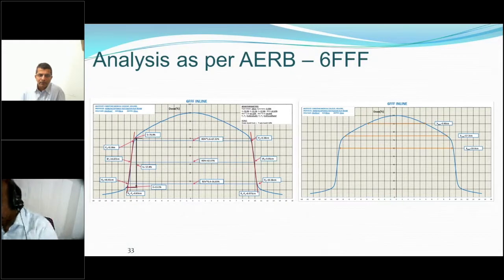One is the surface dose. What was the other one? PDD. PDD is only some 3% less. And if you're using, for example, IMRT or VMAT, these are all compensated. It's not going to affect. So you can use it, but it depends on the distribution you get. You can try both, and whichever you are comfortable with, you should be able to use it. But don't worry about the surface dose. Unless it's a very small field size, the surface dose is not very high with the FFF.